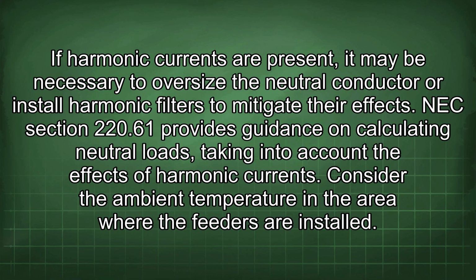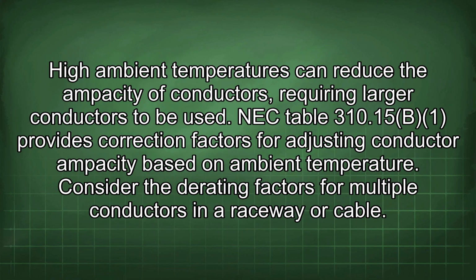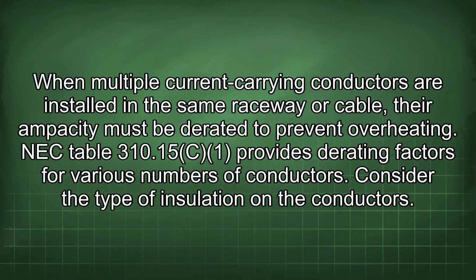currents. Consider the ambient temperature in the area where the feeders are installed. High ambient temperatures can reduce the ampacity of conductors, requiring larger conductors to be used. NEC Table 310.15(B)(1) provides correction factors for adjusting conductor ampacity based on ambient temperature. Consider the derating factors for multiple conductors in a raceway or cable. When multiple current-carrying conductors are installed in the same raceway or cable, their ampacity must be derated to prevent overheating. NEC Table 310.15(C)(1) provides derating factors for various numbers of conductors.